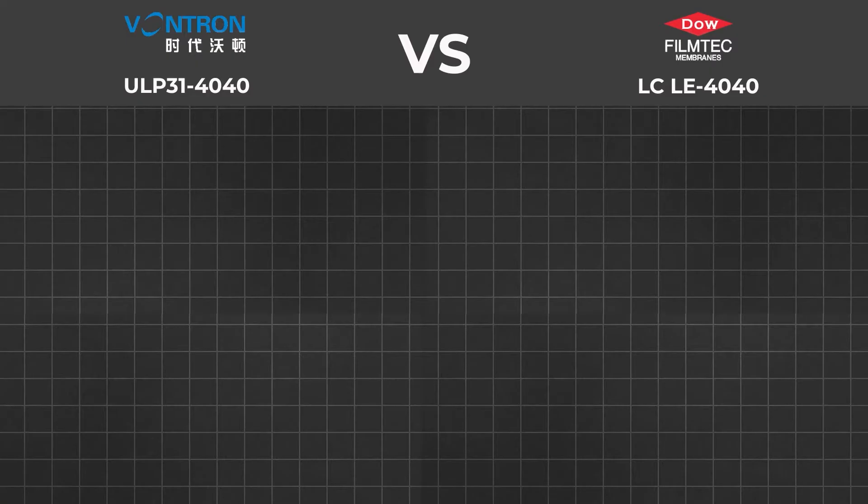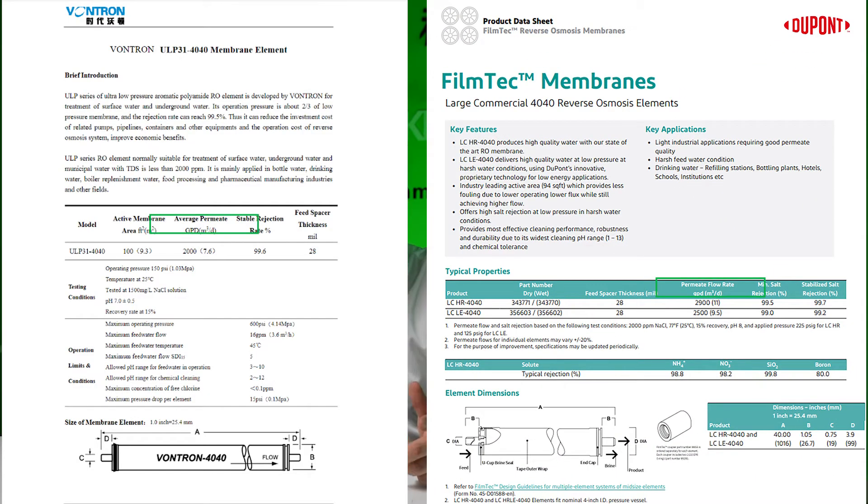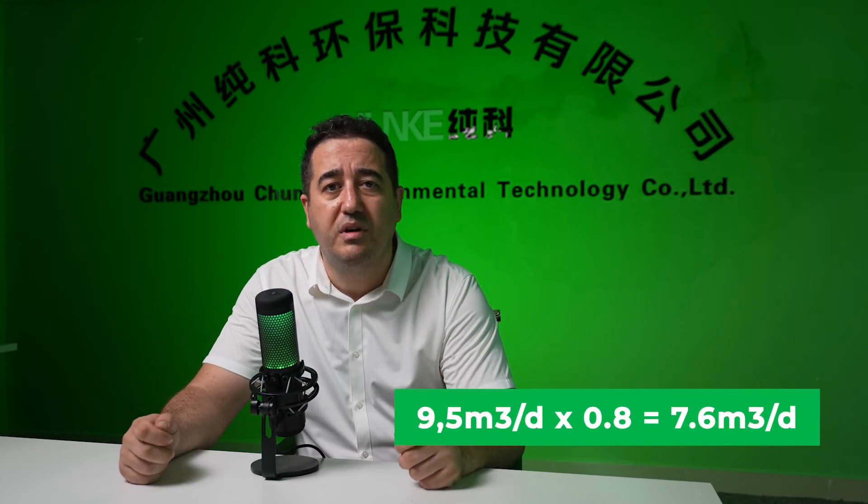Permeate flow rate — permeate means treated, filtered water after the RO system. From the table, Vontron's flow rate is 7.6 cubic meters per day and FilmTec's is 9.5 cubic meters per day. However, Vontron showed an average flow rate in their specification, while FilmTec showed a nominal flow rate that can vary by plus or minus 20%. So if we calculate FilmTec at 20% less, it is about 7.6 cubic meters per day — the same as Vontron. Most water treatment system producers calculate permeate flow rate based on 7.6 m³/day for tap water.